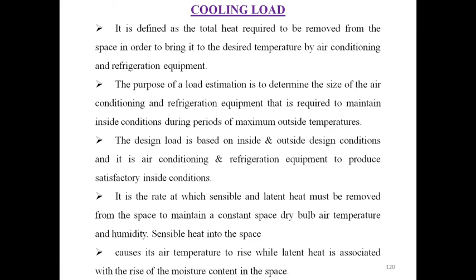The air conditioning and refrigeration equipment must provide satisfactory inside conditions. It is the rate at which sensible and latent heat must be removed from the space to maintain a constant dry bulb air temperature and humidity. Sensible heat causes air temperature to rise, while latent heat is associated with the rise in moisture content in the space.